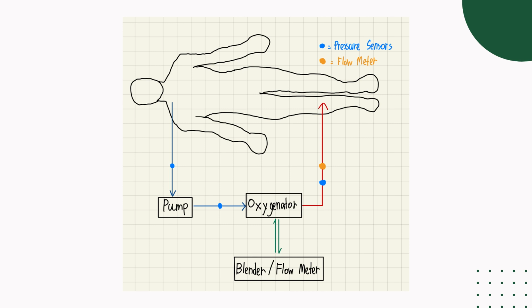Another position for the pressure sensor is the outlet of the pump just before the oxygenator. This one will show a positive value, measuring the amount of resistance from the oxygenator. The last position of the pressure sensor is at the outlet of the oxygenator. The pressure value will also be a positive value, which signifies the amount of resistance past the oxygenator to the patients. So both the pre and post oxygenator pressure sensors here can be used to calculate the change in pressure that occurs within the oxygenator itself, which can tell us whether we have a blood clot or not.